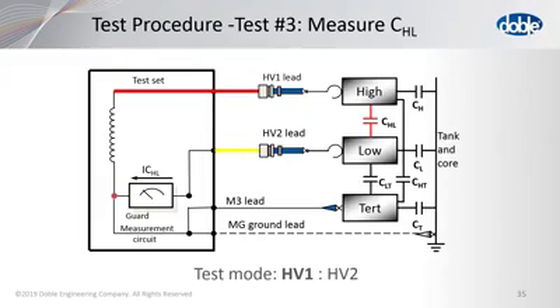Okay, let me just explain what I think he means. If there is a ground for any one of the bushings, that must be removed. Now, one other situation that he might be considering is when you have 2 Y-connected windings, sometimes there is a link between the 2 at the neutral point, and that would have to be disconnected to be able to test those 2 windings separately. If you cannot get to the link, then you are forced to test that as 1 winding. I think that's what he probably was questioning.